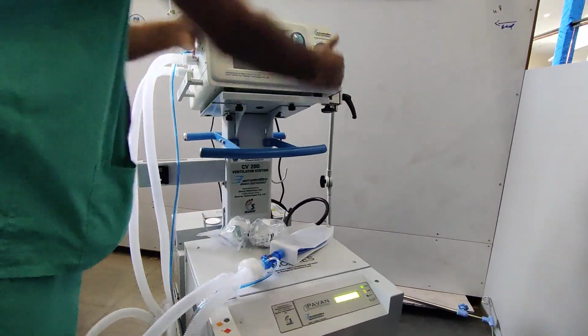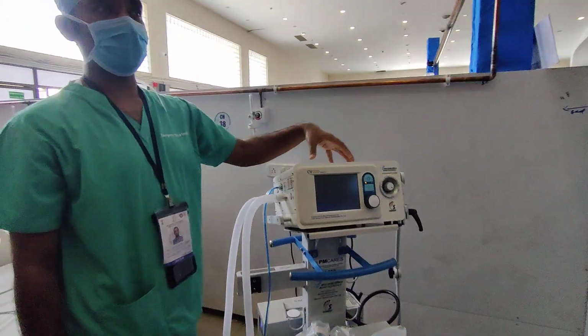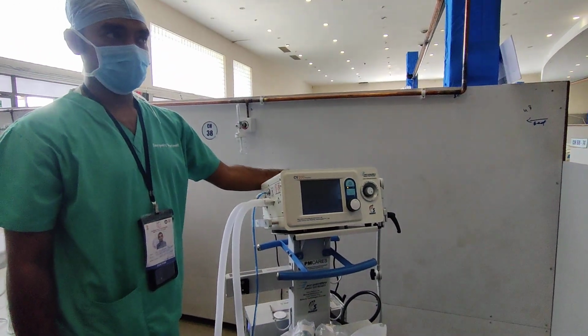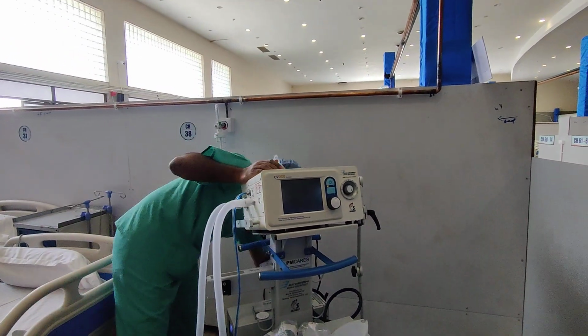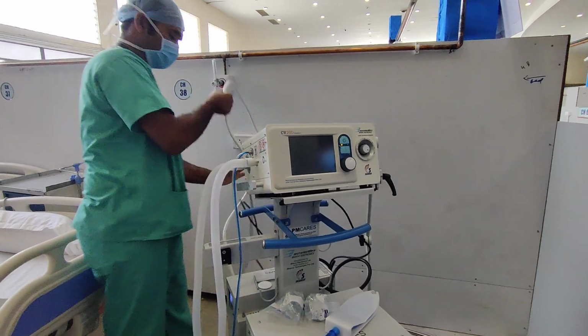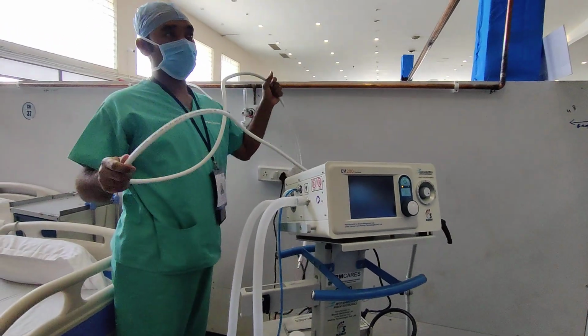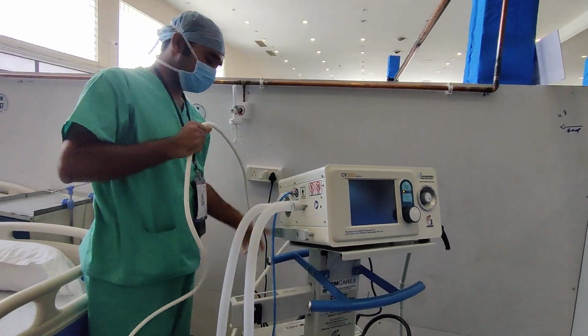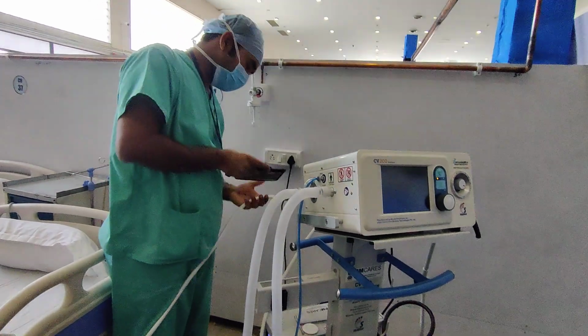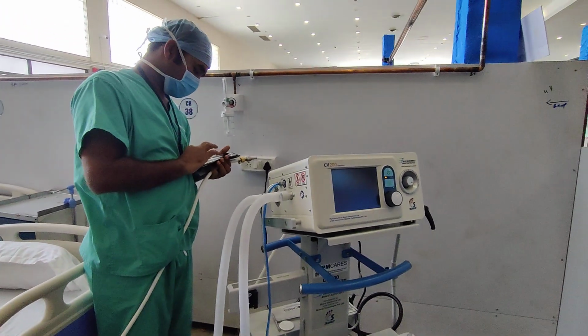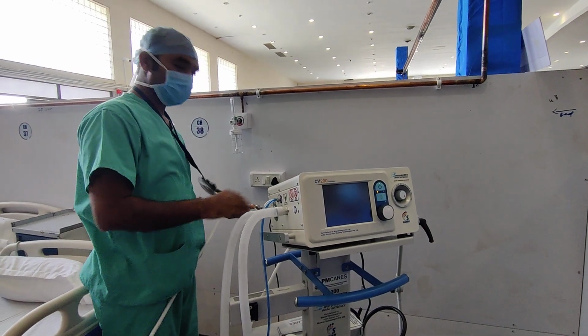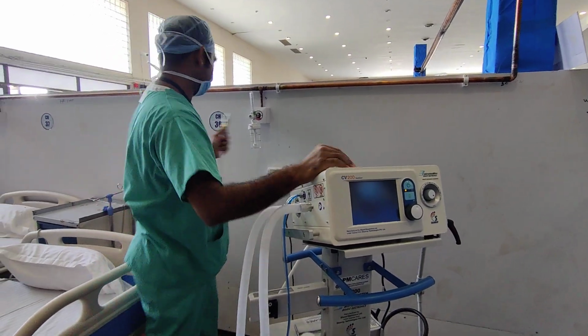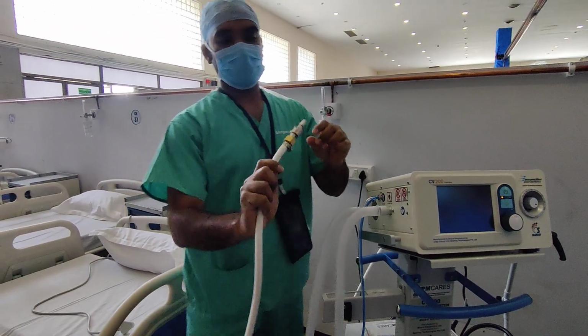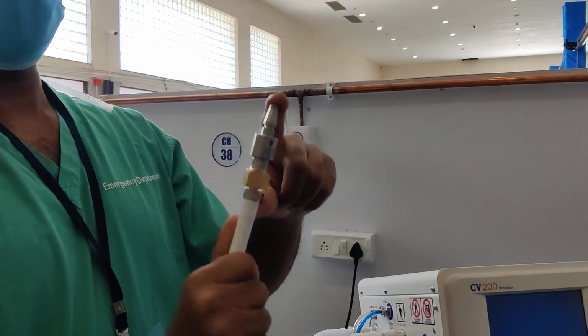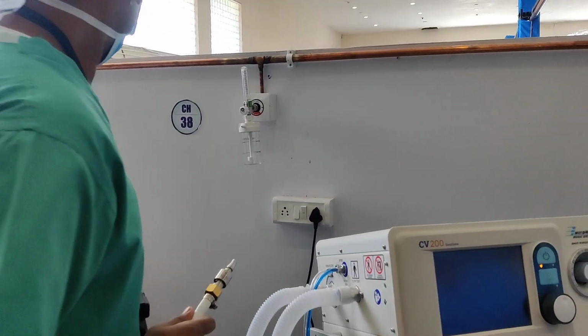Now how to switch on the ventilator. Before we move on, the ventilator needs air and oxygen. We already discussed air. Let's discuss oxygen before we switch on our machine. This step is very important. You need to connect oxygen. You need to supply oxygen to the ventilator before you start using the ventilator. So this is an oxygen knob. You need to connect this to your oxygen supply channel.